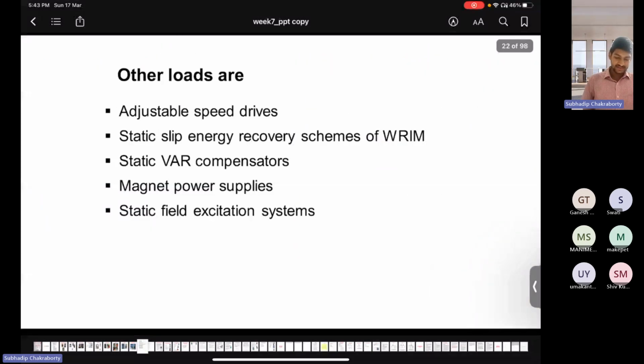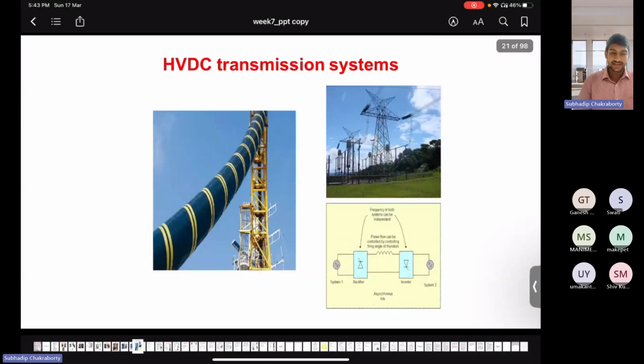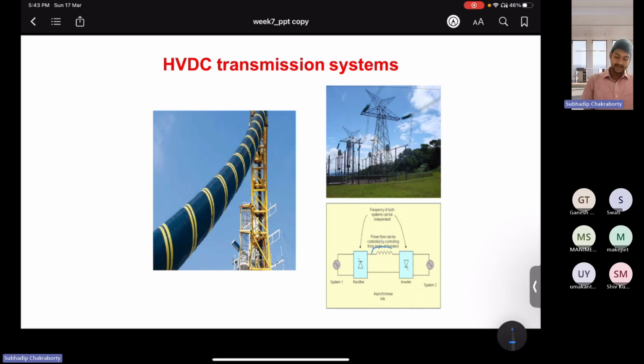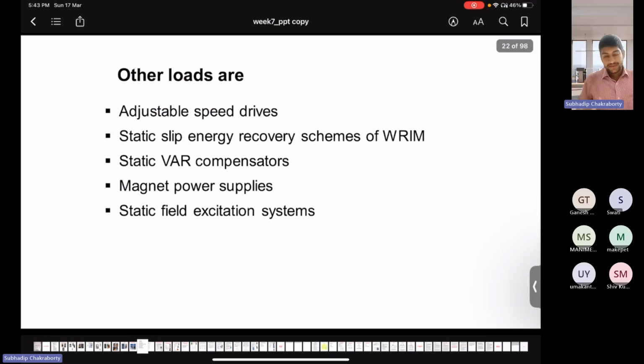As you might have seen in the lecture also, in the HVDC transmission lines there also we have current quality problems because of the presence of these thyristor-based converters and the large inductance that you want to use to make the DC side current continuous, right? But it will lead to harmonics and reactive power at the AC mains. So you need compensating devices for that, such that your grid side power quality and power factor requirements are maintained.